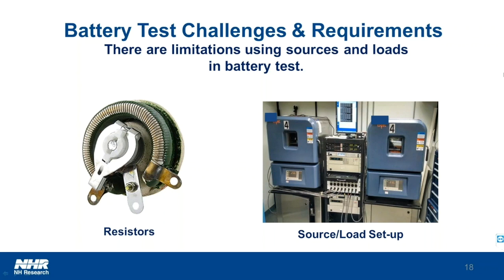Last generation battery cyclers also struggle to meet the demands of modern battery testing. Past generation cyclers are very slow. They have a lot of output impedance, making them unable to perform fast transients. They tend to be noisy and they can lack accuracy as well.